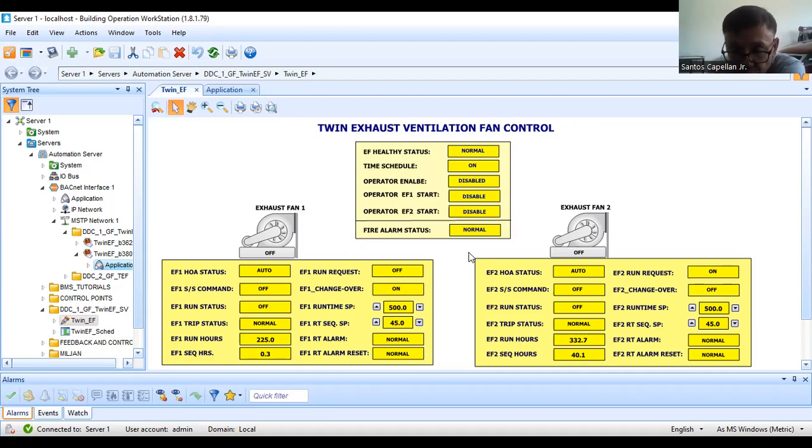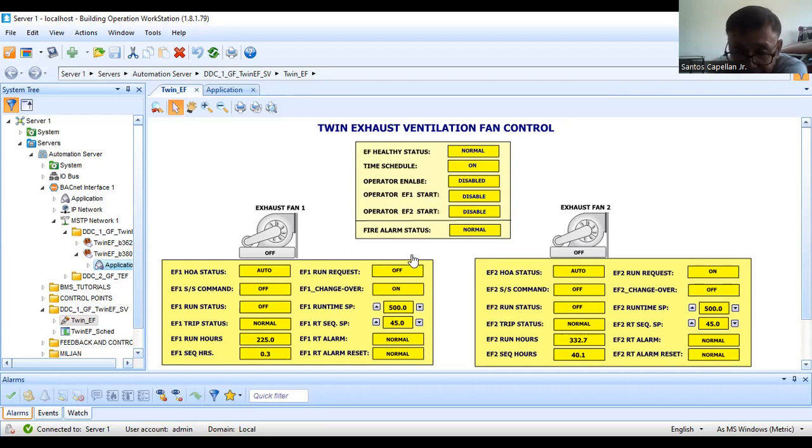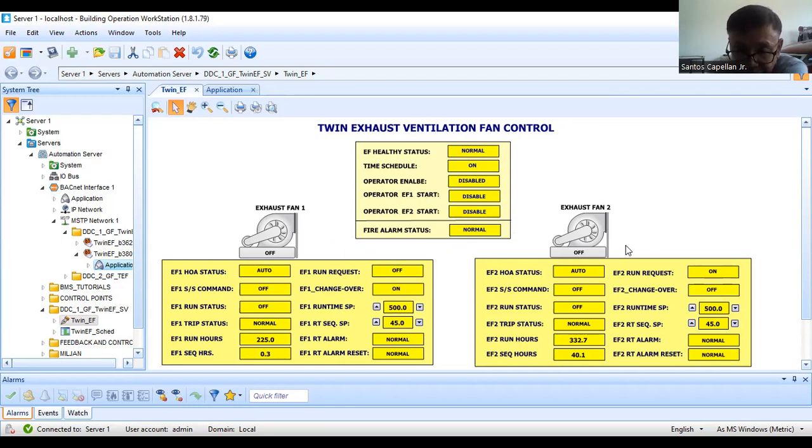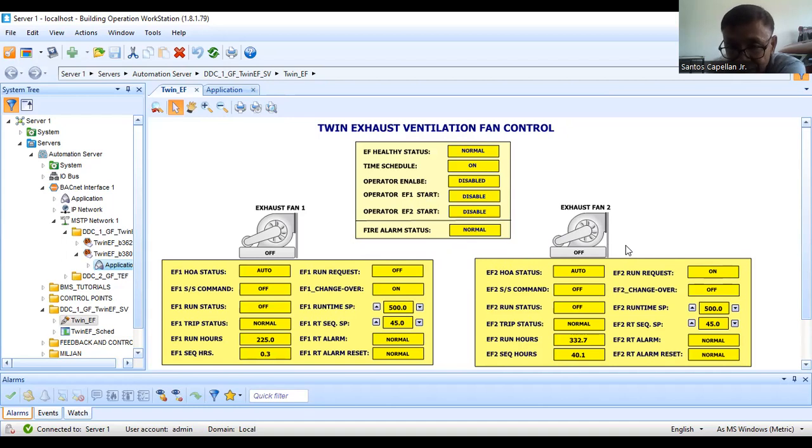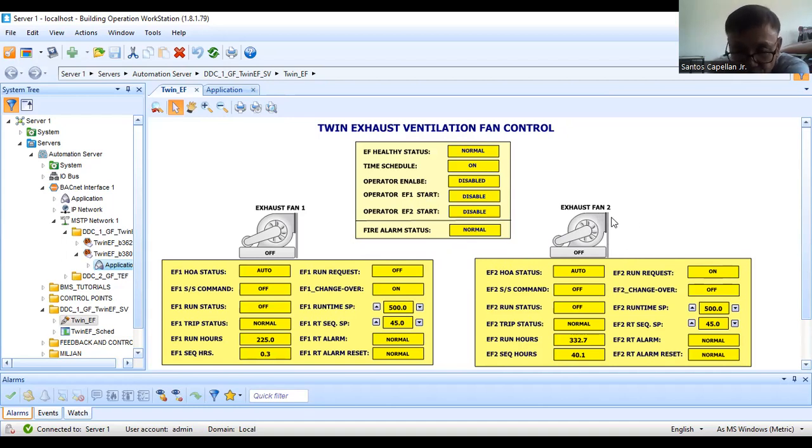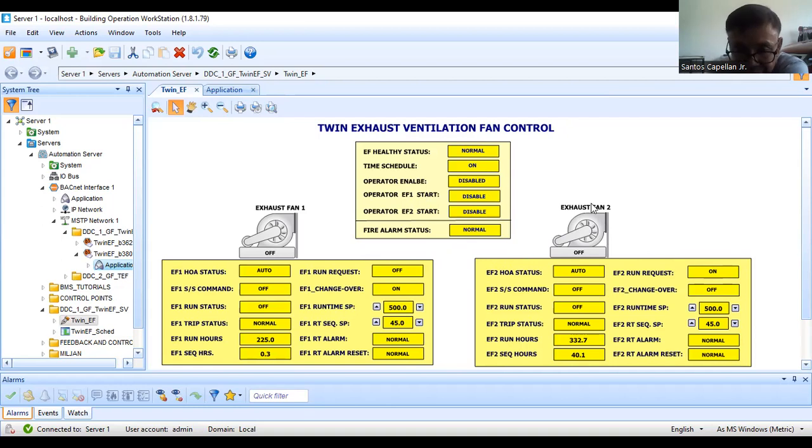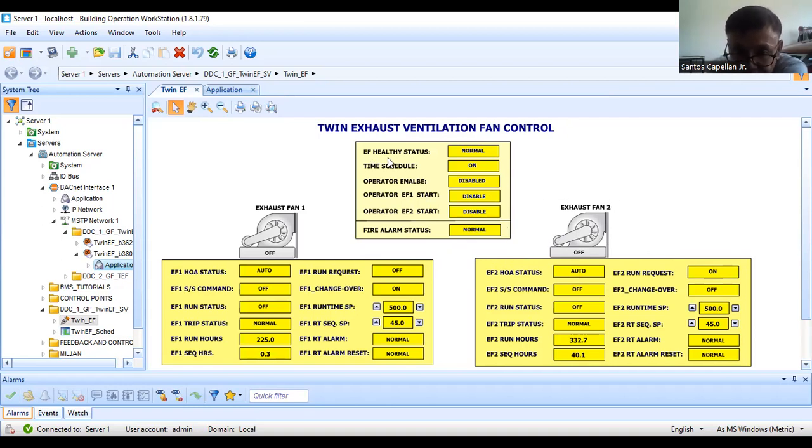In that room, there should always be one exhaust fan working. The reason is, this battery can emit toxic fumes, so we need to vent it out. There should always be one fan running.